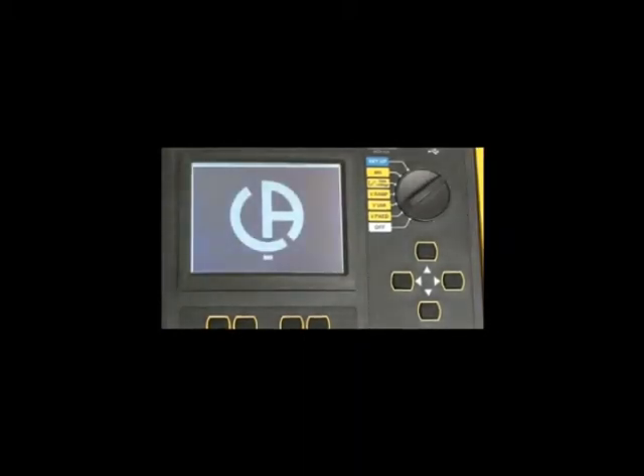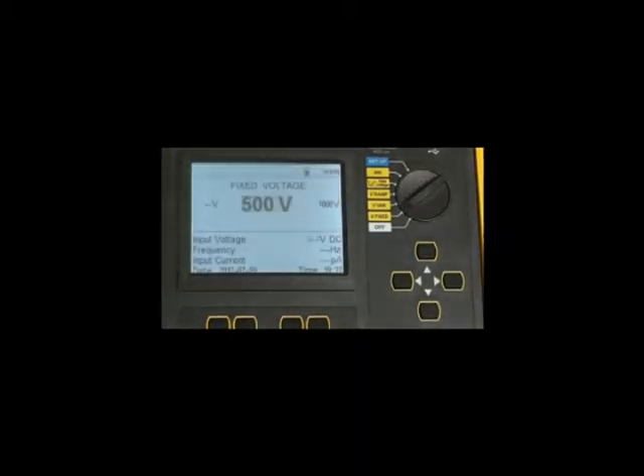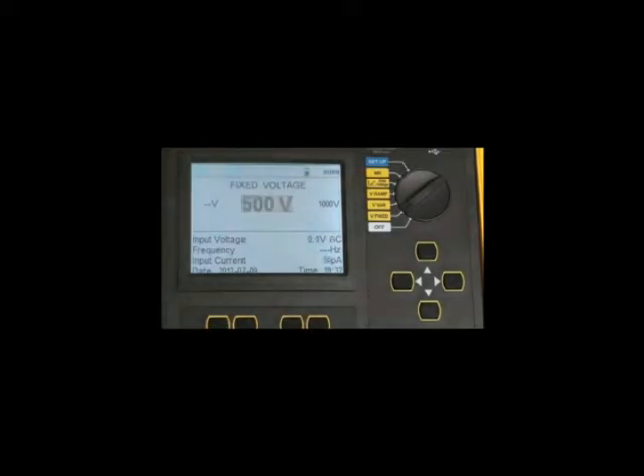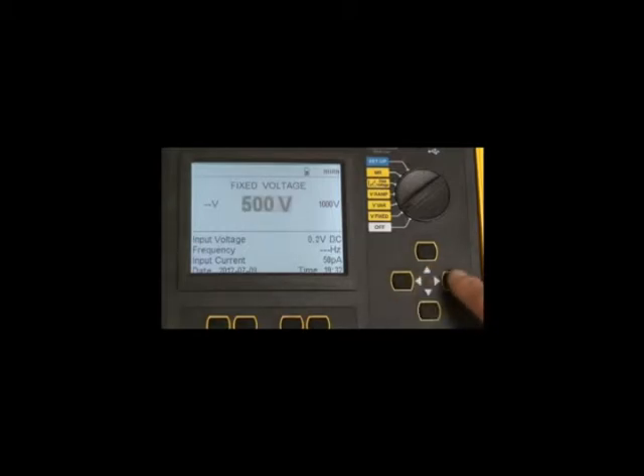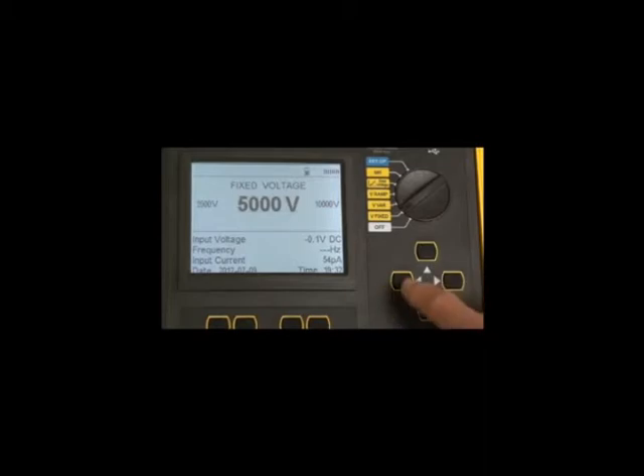Individual test functions are directly accessed using this rotary switch. In the V fixed position, the user can run a test anywhere from 500 volts to 10 or 15,000 volts based on model by simply accessing the test voltage using the navigation keys.